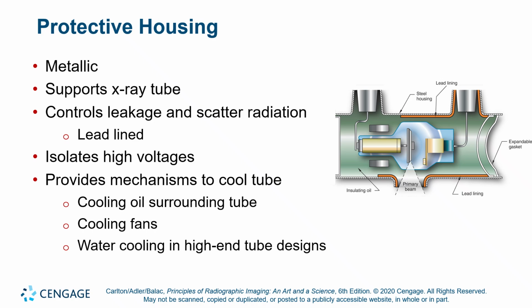Water cooling in high-end tube designs. That's going to be your CT scanner primarily. Okay. So the CT scanner has a refrigerant coil, water-based. It probably is the same coolant as you find in the radiator of your car. So that's ethylene glycol, that's antifreeze. Okay. But that's ethylene glycol diluted 1-to-1 with water. So it says water cooled here, but it's probably antifreeze cooled.